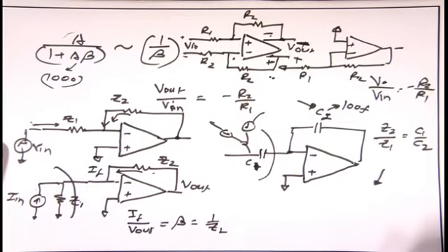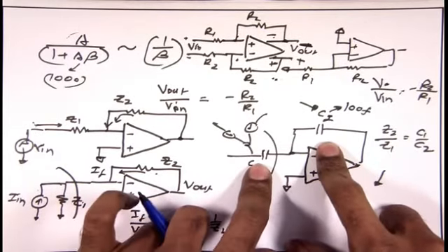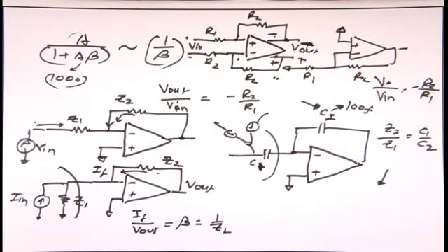So you were proceeding towards the stability analysis of the main amplifier, and first of all, we decided why to choose capacitive feedback as an option for our design. That is dictated by the electrode impedance. The electrode has very high impedance, therefore we don't want to use R1, R2 as a feedback because it will use very large resistance values.